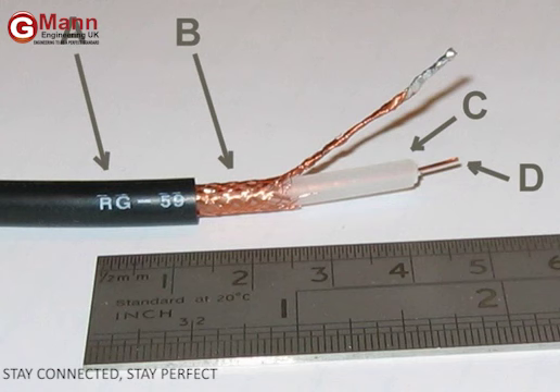External fields create a voltage across the inductance of the outside of the outer conductor between sender and receiver. The effect is less when there are several parallel cables, as this reduces the inductance and, therefore, the voltage. Because the outer conductor carries the reference potential for the signal on the inner conductor, the receiving circuit measures the wrong voltage.